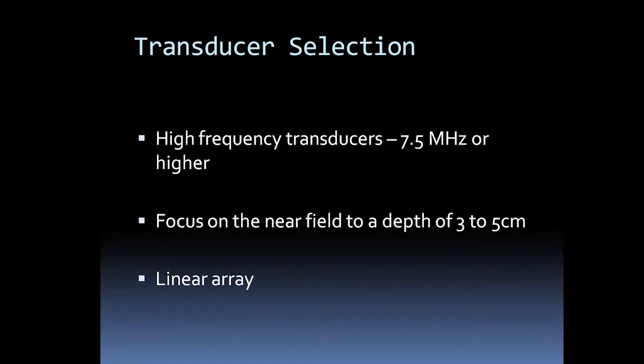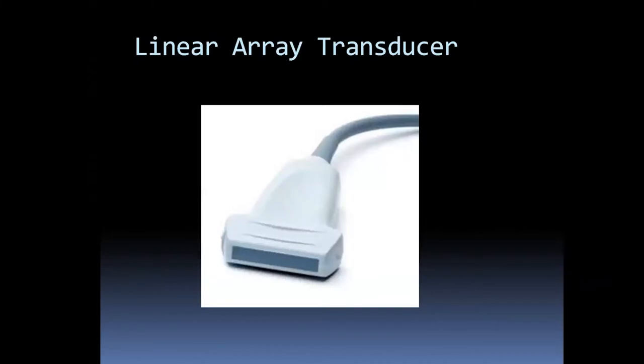Transducer selection: when you're doing ultrasound-guided procedures, you want to make sure you have a high-frequency transducer, at least 7.5 megahertz or higher. You want to focus on the near field to a depth of 3 to 5 centimeters, and you want to make sure it's a linear array transducer. This is an example of a linear array transducer, so it's not that body transducer you guys use for your other rotations that's curved. This is flat.